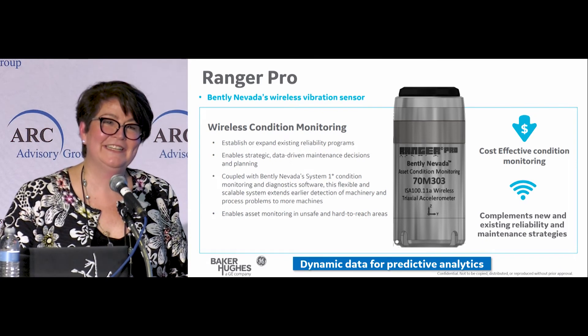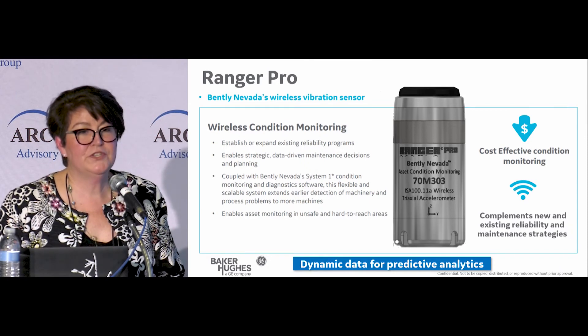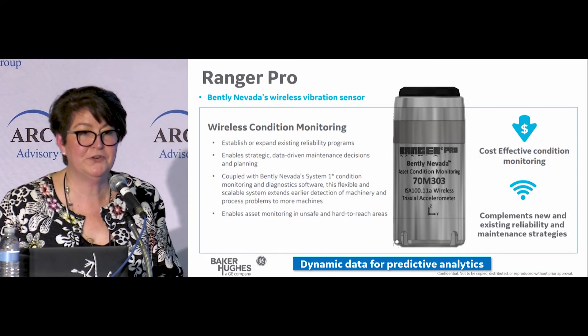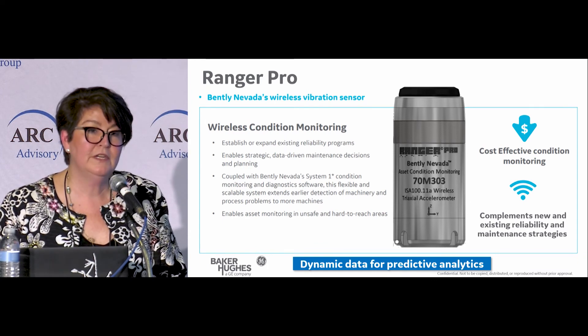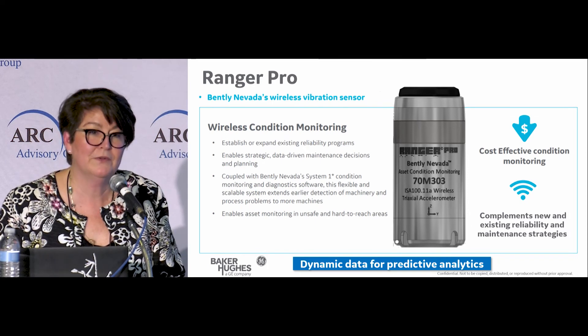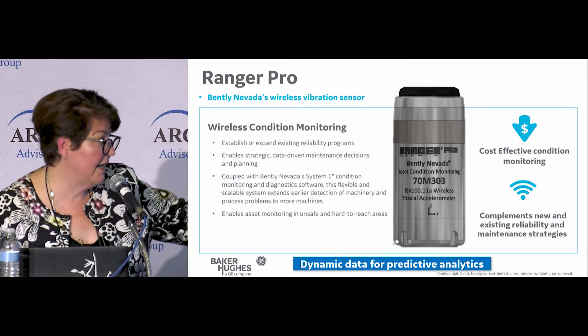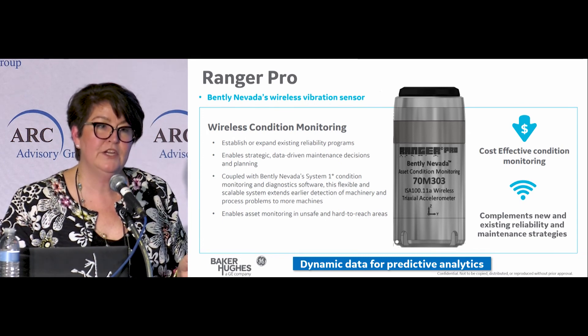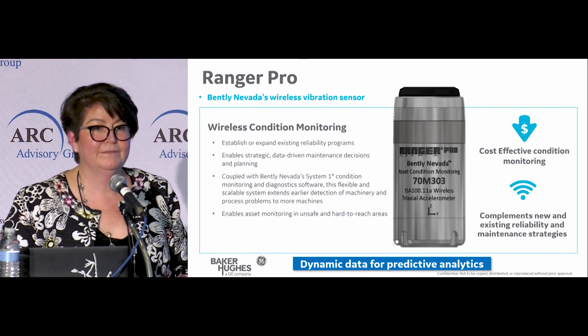How do you attach it to your fan motor or whatever? There are actually three ways. You can have a magnetic base — it's a sturdy, heavy-duty magnetic base, so once you put it down you have to wiggle it to get it off. Some may want to take one sensor around, but at approximately $1,000 a sensor I think they should just buy two. There's also an epoxy mount and a screw mount. There is a certain orientation required, but the design of the ring on the bottom gives you flexibility to adjust it if it's not perfectly aligned, so you can get that proper X, Y, and Z measurement.